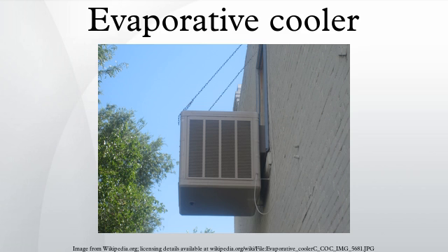Evaporative cooler designs. Most designs take advantage of the fact that water has one of the highest known enthalpy of vaporization values of any common substance. Because of this, evaporative coolers use only a fraction of the energy of vapor compression or absorption air conditioning systems. Unfortunately, except in very dry climates, the single-stage cooler can increase relative humidity to a level that makes occupants uncomfortable. Indirect and two-stage evaporative coolers keep the RH lower.